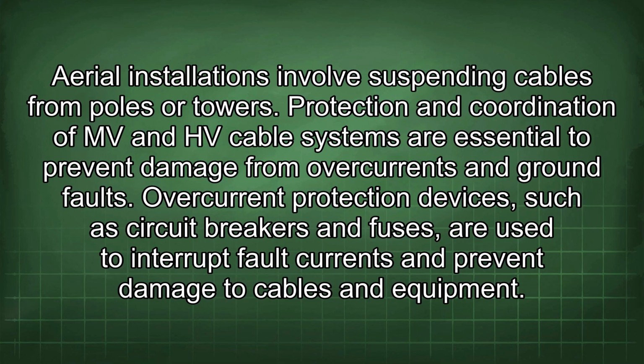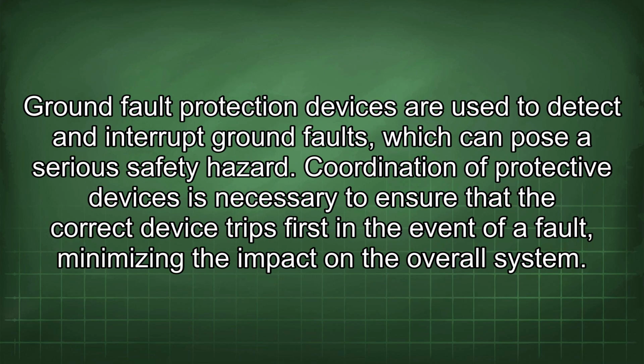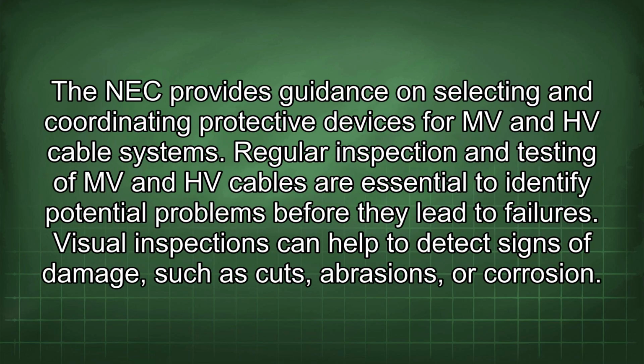Protection and coordination of MV and HV cable systems are essential to prevent damage from overcurrents and ground faults. Overcurrent protection devices such as circuit breakers and fuses are used to interrupt fault currents and prevent damage to cables and equipment. Ground fault protection devices are used to detect and interrupt ground faults, which can pose a serious safety hazard. Coordination of protective devices is necessary to ensure that the correct device trips first in the event of a fault, minimizing the impact on the overall system. The NEC provides guidance on selecting and coordinating protective devices for MV and HV cable systems.